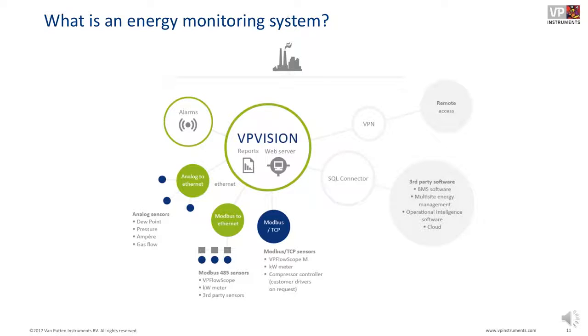We can also connect Modbus TCP sensors. Think about our new VP Flowscope M that comes with a Modbus TCP output. With that sensor, we do not need to run those long cables. We can directly connect it into our nearest Ethernet connection in the plant, provide the flow meter with an IP address, and avoid putting in extra I/O modules. Now the VPVision has a direct connection through the company network to the flow meter. And that's how they are communicating and sending their data.